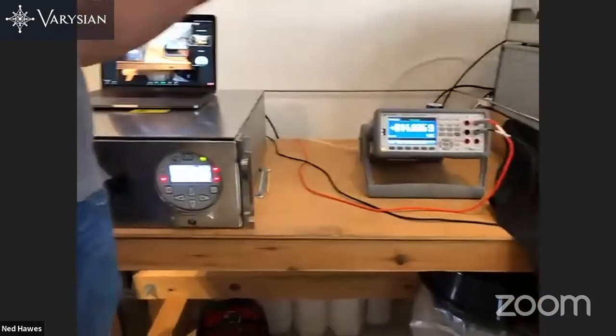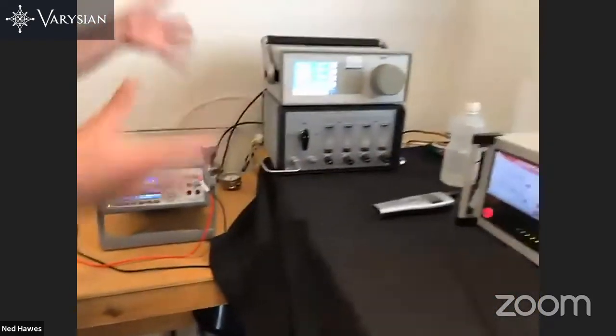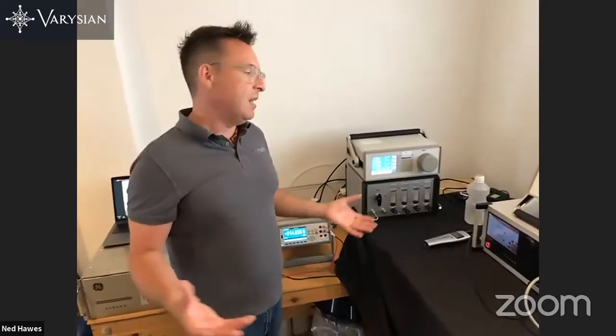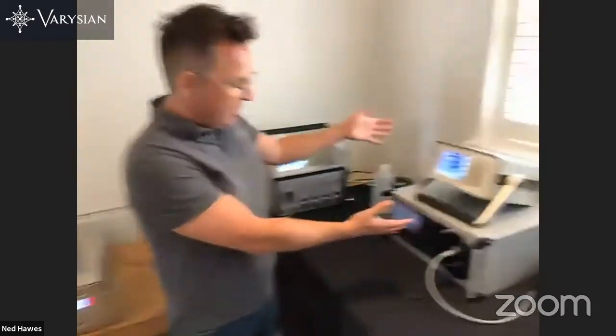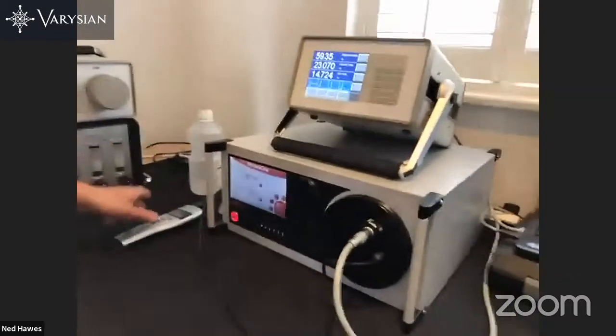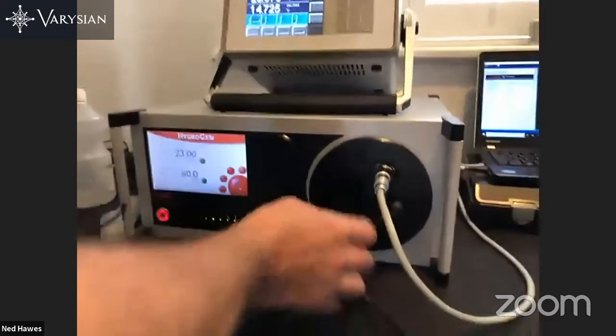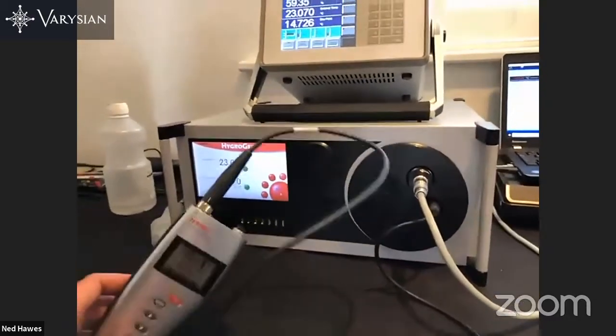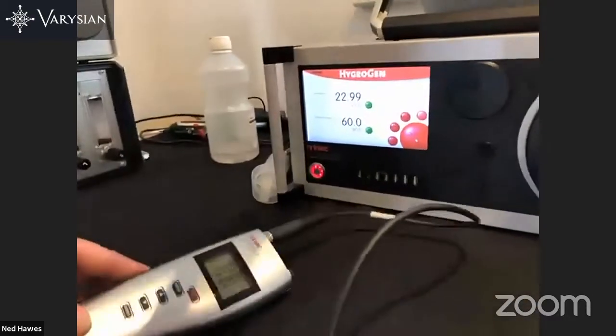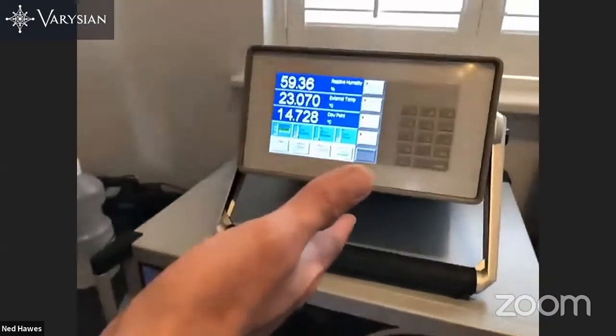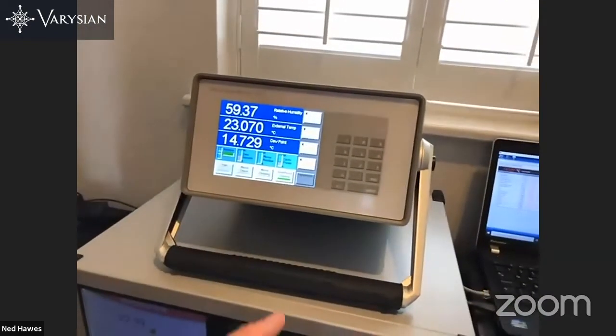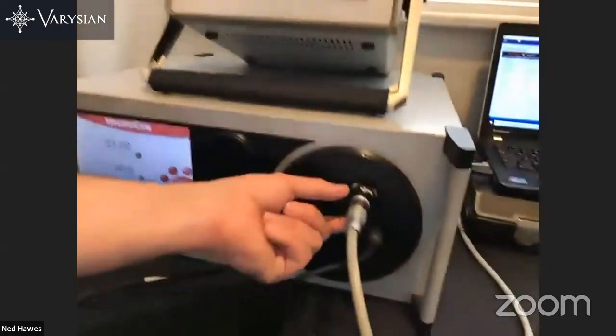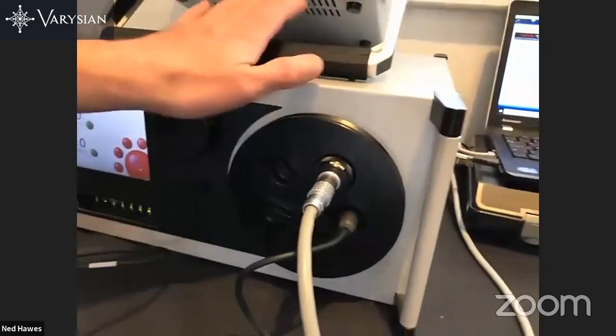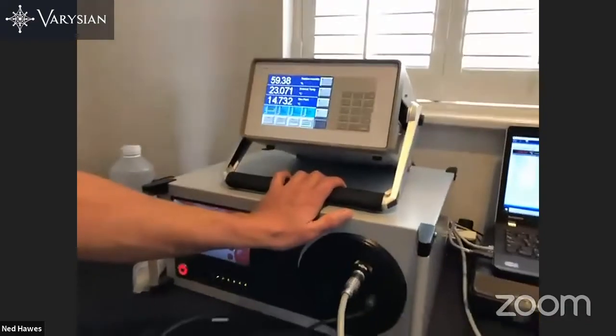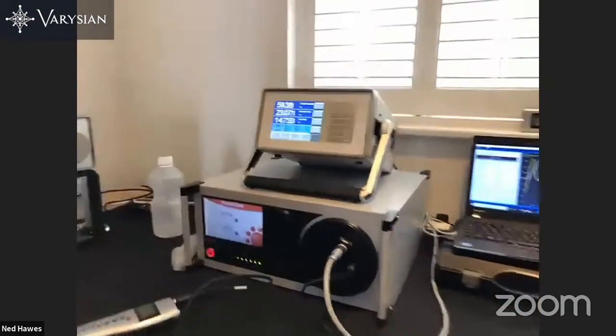But we do that quite frequently. We take the whole rig on site to do on-site calibrations at power stations, for example, in the UK. Then we have the Rotronic HygroGen. Inside the Rotronic hydrogen is a Rotronic RH probe. And then on top we have the 473 that Patrick was talking about with the RP2 probe through the door of the HygroGen. I'm going to come back to this one and show you a little bit more detail shortly.